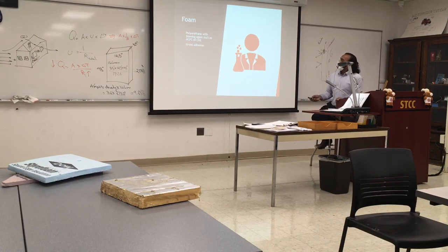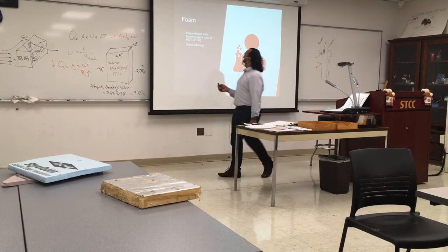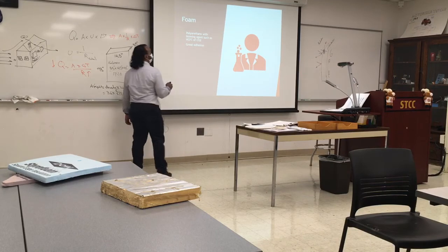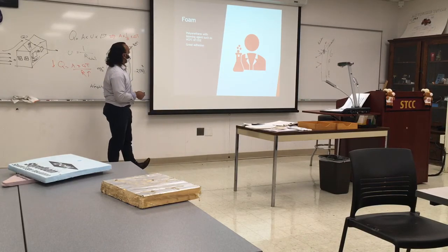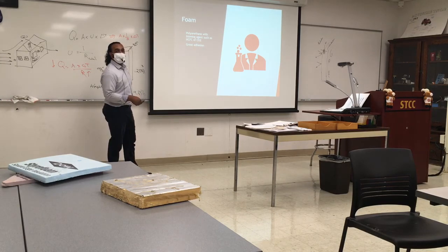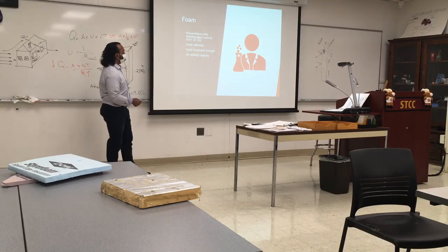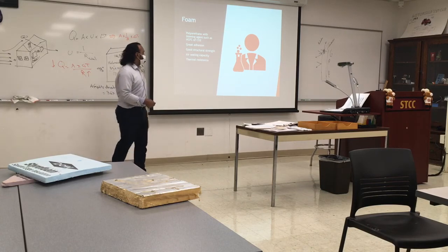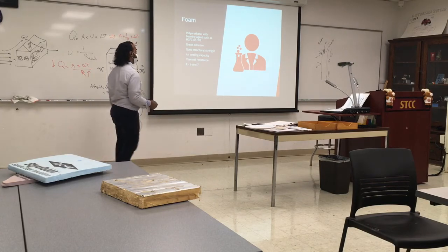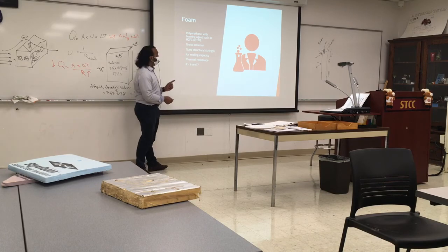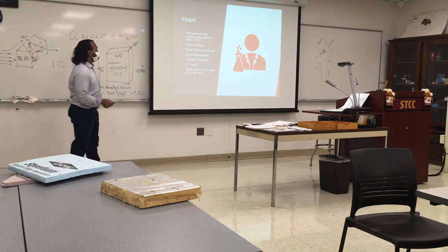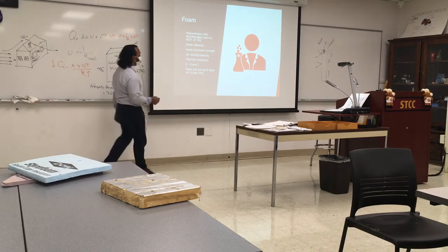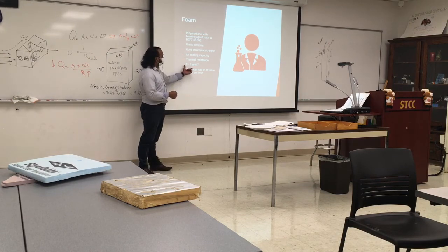Foam is a polyurethane with a blowing agent like CO2 or HCFC, which is not good for the environment. It has great adhesion. Yeah, good luck trying to get that out of your hand. It's really messy. Good structural strength, depending how you spray it. It has air sealing capacity. Good thermal resistance, R6 and 7, which is really good. That's per inch, by the way. Foam has an R value of 3.6 per inch, and I think this is also per inch.